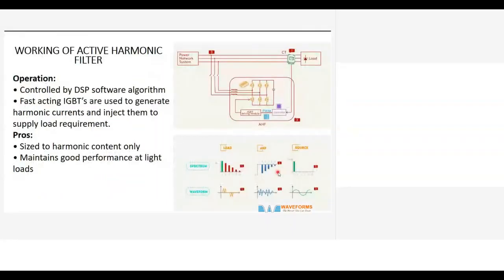You will see the harmonics generated here, and then you see the reverse harmonics generated by the active filter, and then you eliminate the other harmonics. So this is how the active filter does its job of cancelling harmonics. But normally they are very expensive.